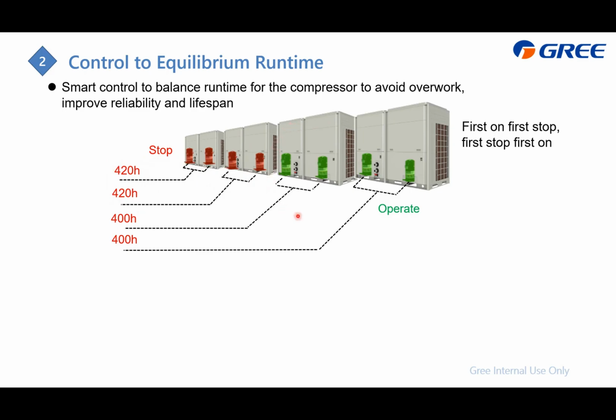Then we will turn on this one. This is only 400 hours, and after it operates for another 20 hours, this 4 will stop, and then we turn on this one. The principle is just like this: the compressor that turns on first will turn off first, and if it is first to turn off, then the next time it will be first to turn on. Just balance the operating time to enlarge the lifespan.